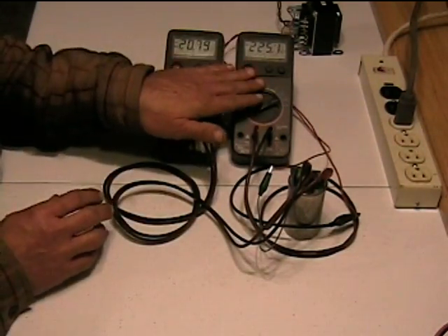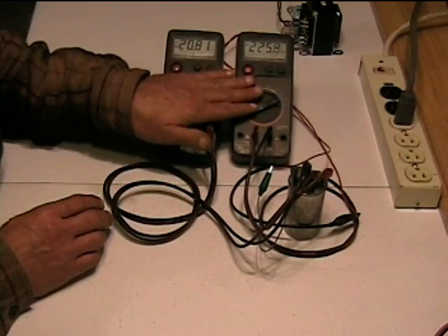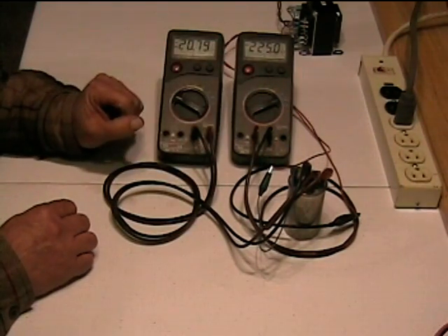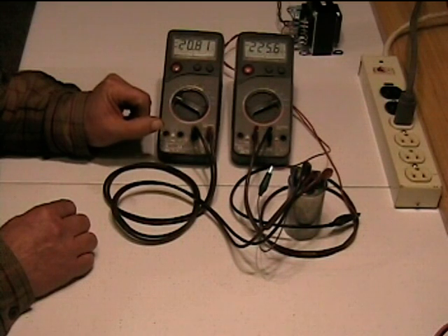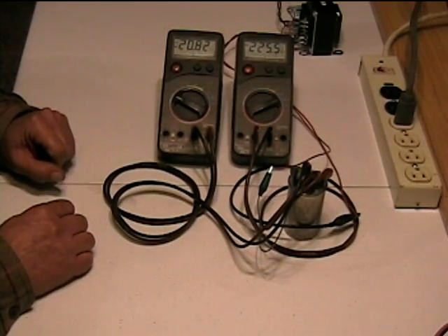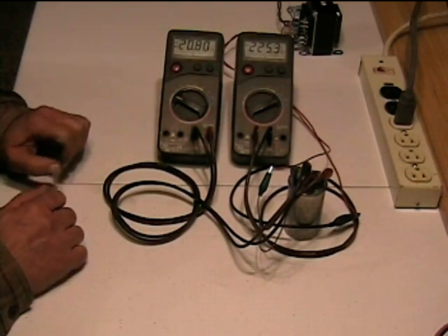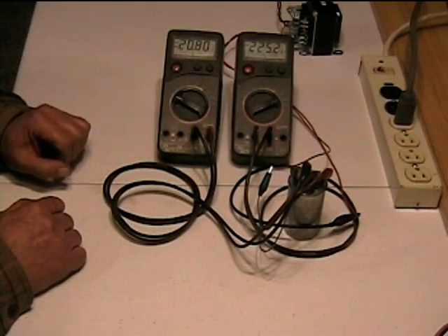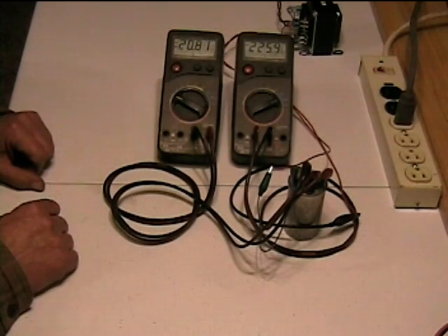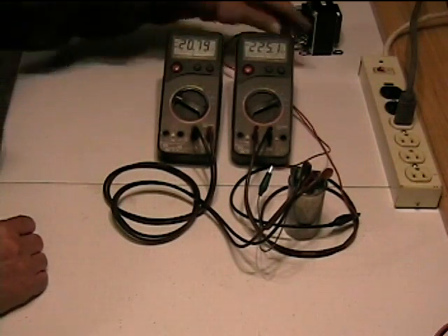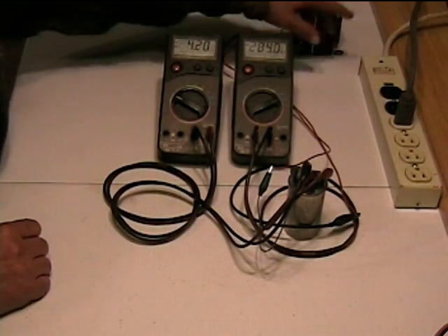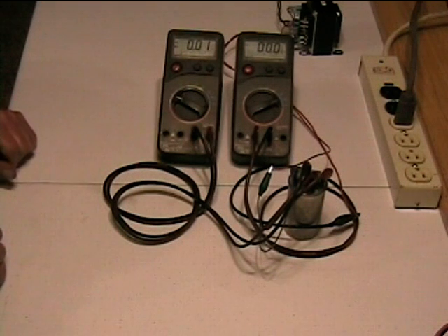As you noticed, I left this turned on. You would only want to turn it on for a second or two to take a reading, especially if you're dealing with a larger capacitor like a motor starting capacitor, because those are only meant to come into play for about a half second while the motor starts. And even though we're operating at a lower voltage so that the current would be lower, it would be passing a lot of current through the capacitor right now. It could be several amps, and that would cause the capacitor to heat up. So you only want to turn this on momentarily, get your reading, shut it back off. That's a very simple thing to do.